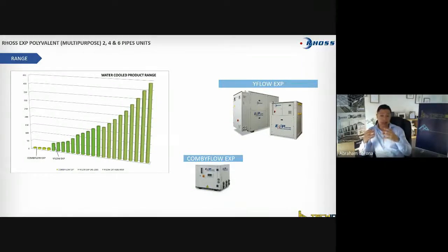As a chiller and heat pump manufacturer, in my experience, at least 70% of the time when someone gets an alarm, it is an installation issue. First thing, we have been doing chillers for so many years. It's the same chiller that we've been making on our manufacturing line. It's tested and European certified. When a chiller manufacturer makes a mistake, we're the ones who raise our hand and say, look, we made a mistake, we've got to fix it.